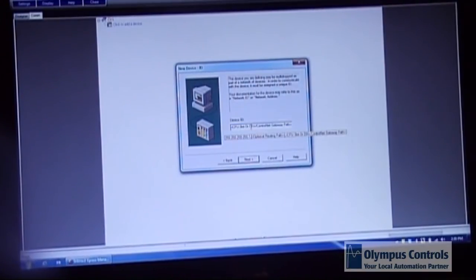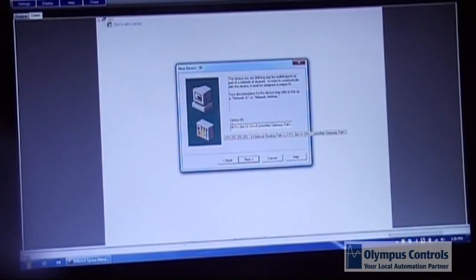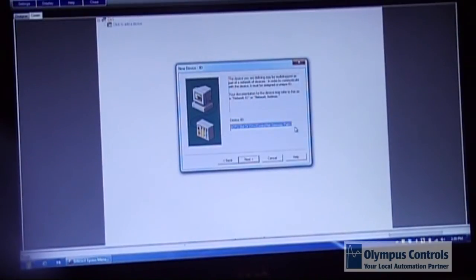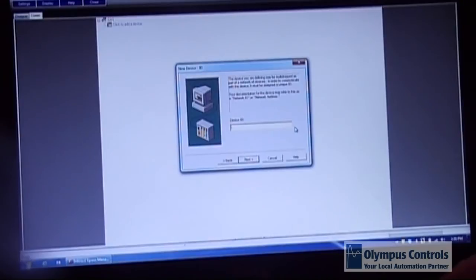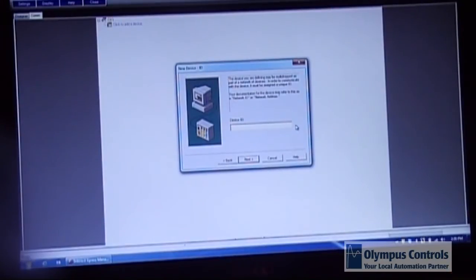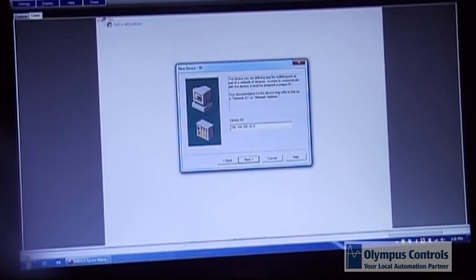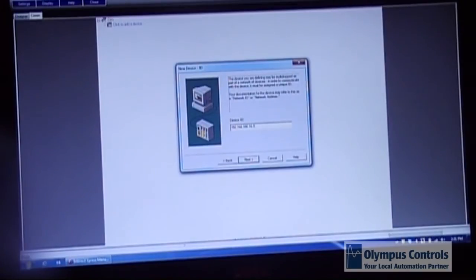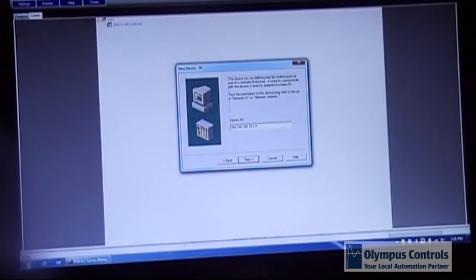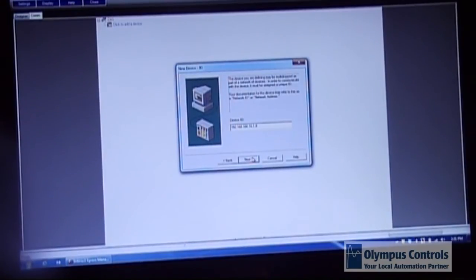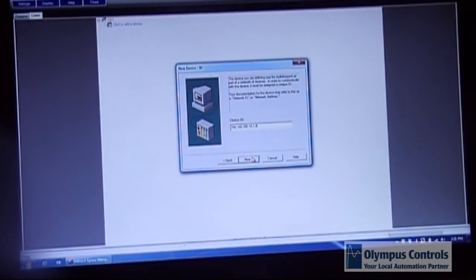At this point you have to give it the IP address of the processor which you can get from your PLC. So I'm entering 192.168.100.10 and then comma 1 for the port ID and comma 0 for the slot the CPU resides in. For Allen Bradley that's the appropriate way to address these.